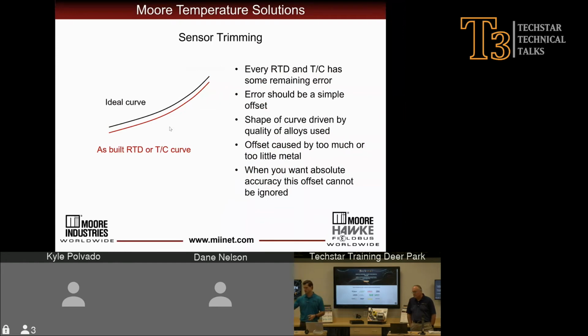So every RTD or thermocouple has some remaining error in it. Now, this is just due to us taking a coefficient that I mentioned earlier and applying it to a millivoltage or a resistance and expecting that to equate to an exact temperature measurement. Being that there's human errors and that there's always some element of our temperature measurement that's not 100% perfect, these errors could be caused by the purity of metals used, or could be caused by the length of extension wire. So there's always going to be a little offset from our ideal curve to our RTD and thermocouple curve, but there's ways that we can get our RTD and thermocouple curve more defined to our ideal curve.